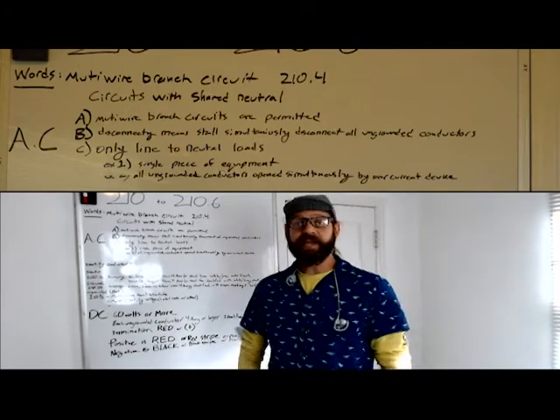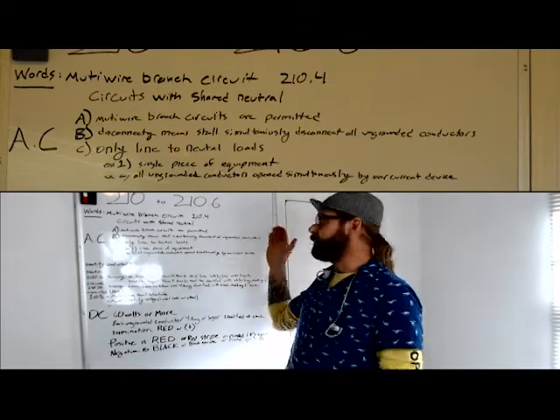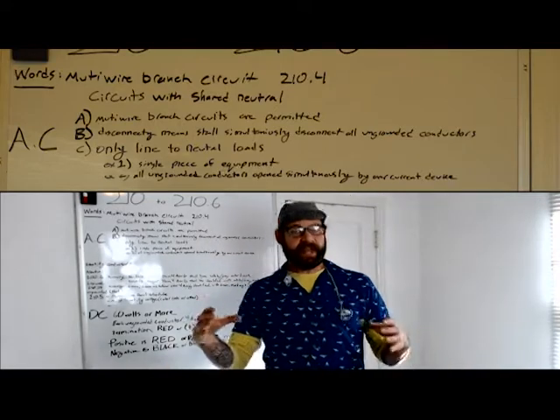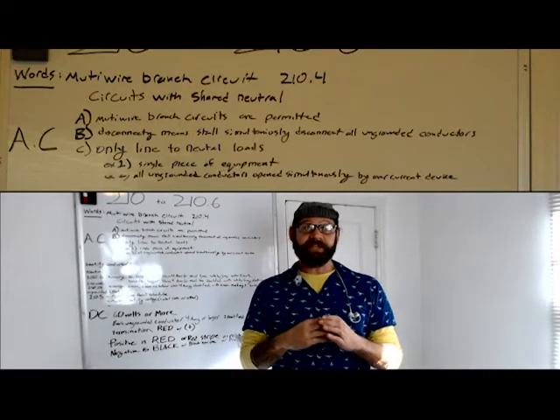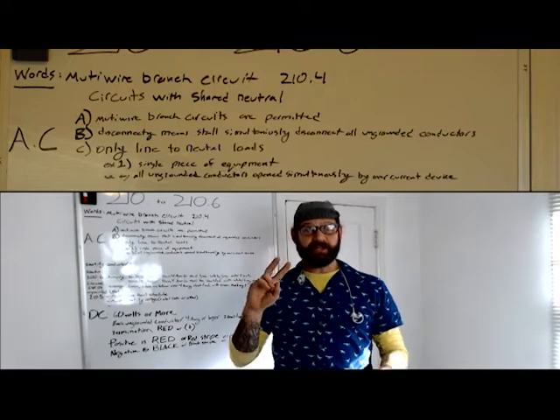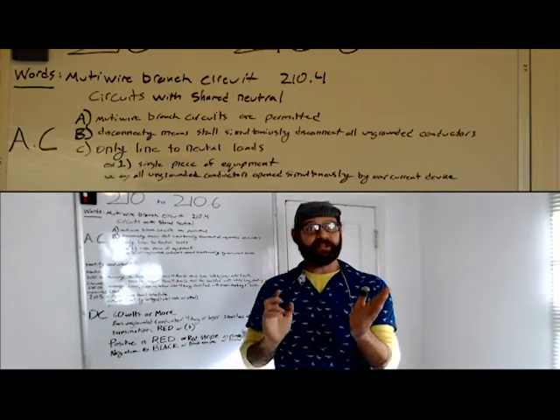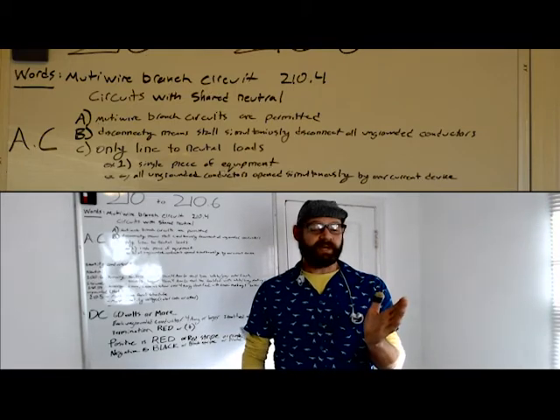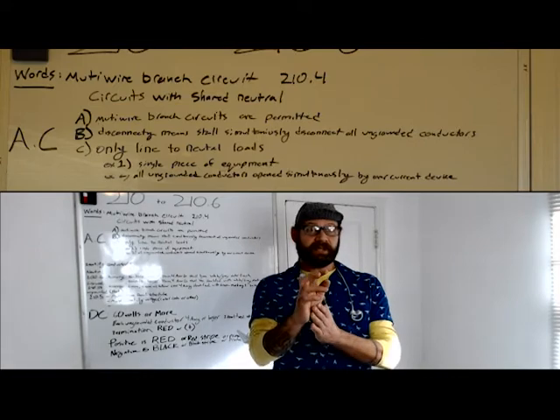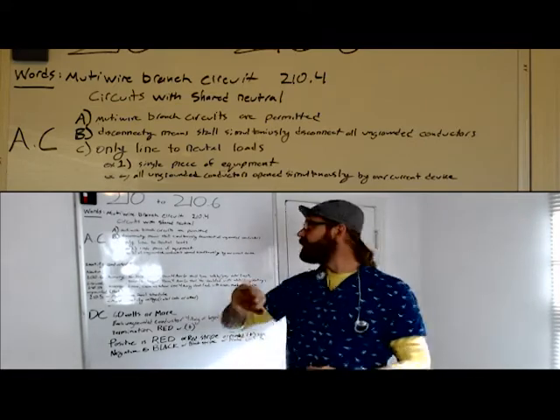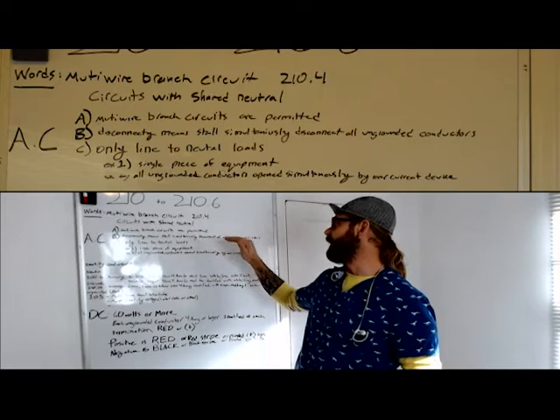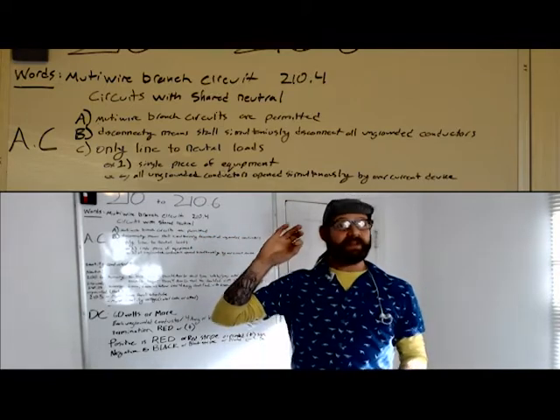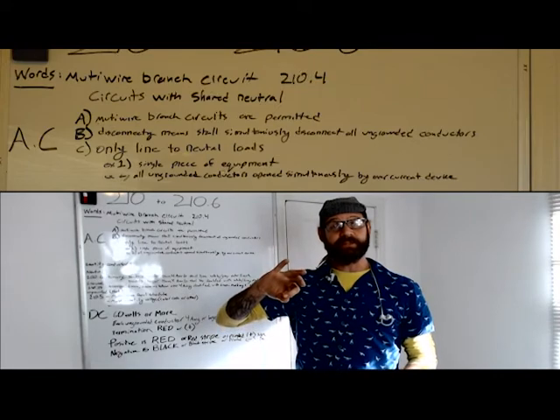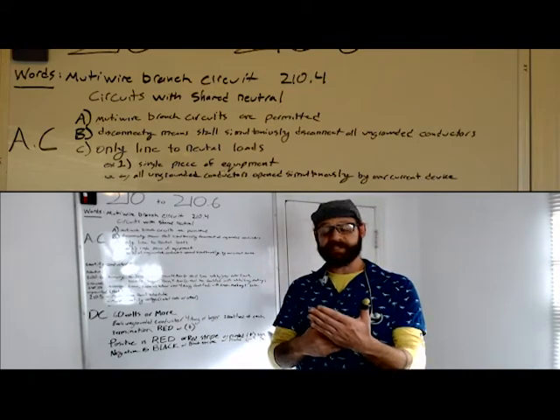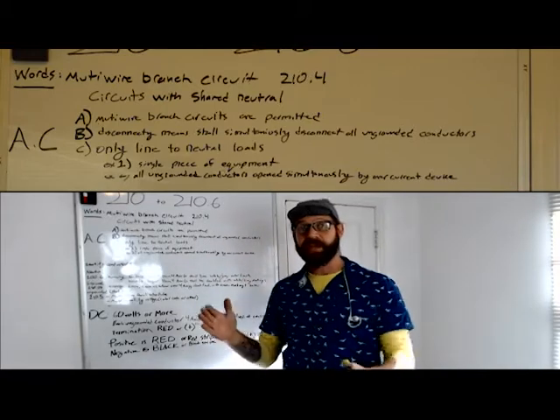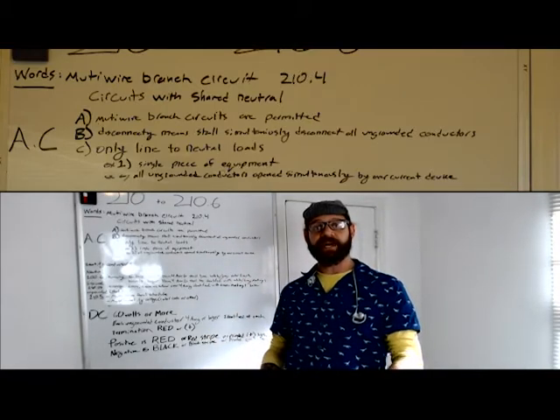210.4(B), disconnecting means shall simultaneously disconnect ungrounded conductors. So what this is essentially saying is that the circuit breaker for a multi-wire branch circuit, if it's 2 hots and a neutral, is going to have to be a 2-pole breaker. It's going to have to disconnect the 2 hots at the same time. If you were to have 2 single-pole breakers, it wouldn't meet this qualification because it wouldn't simultaneously disconnect all ungrounded conductors. So if you have 3 conductors and a neutral, you're going to have a 3-pole breaker that simultaneously disconnects all ungrounded conductors. This is a thing inspectors get jammed up on all the time. You should pay attention to it.